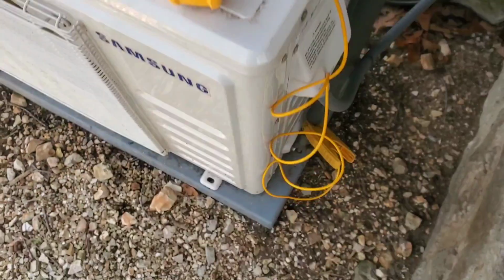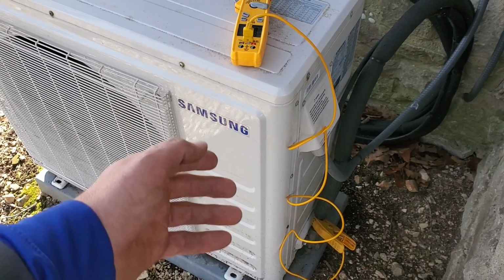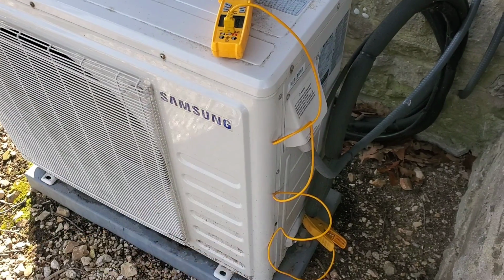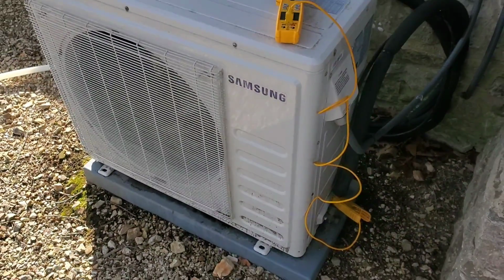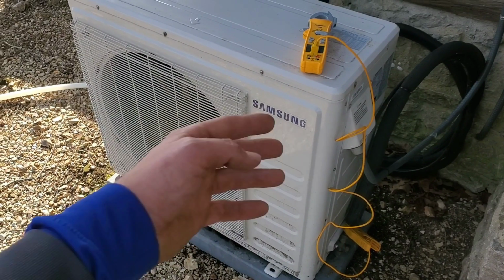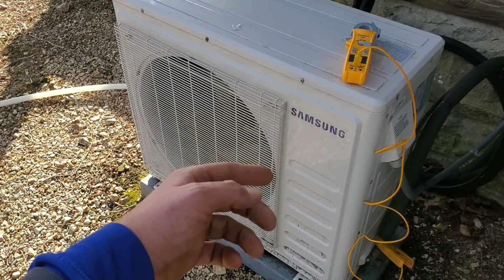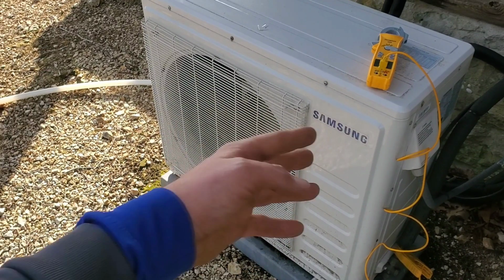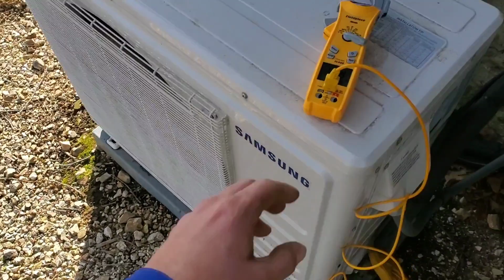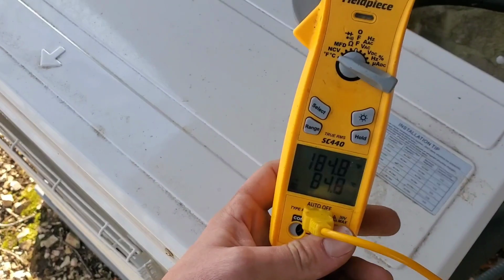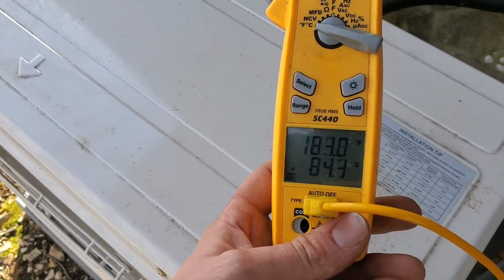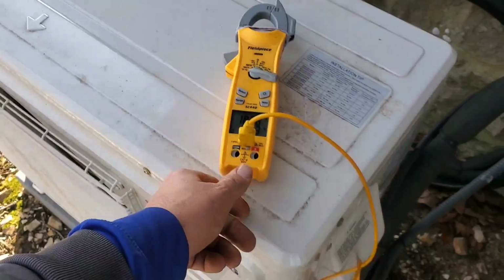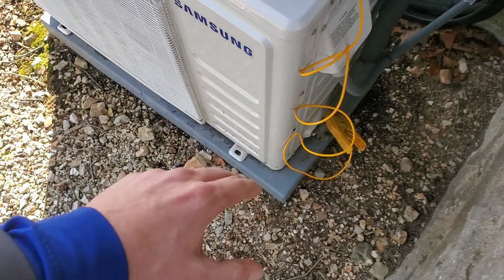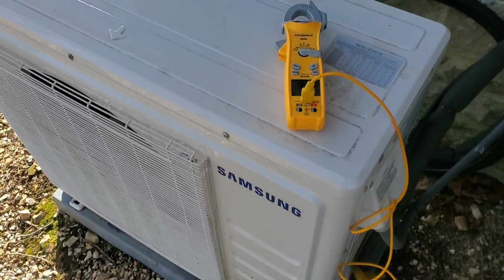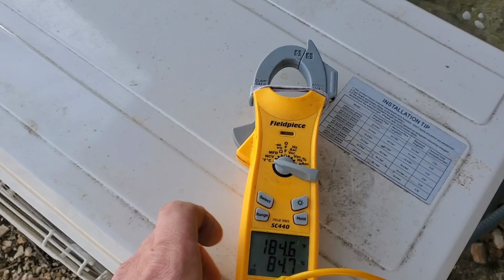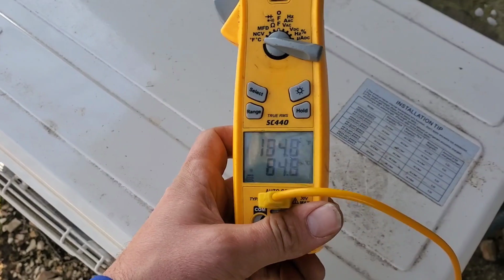It's getting close. It's definitely close to the 99 degrees because it's 180 degrees on the hot gas line, which is going into the indoor heat exchanger. So these units, they reach 99 degrees on the indoor coil, and when they measure that temperature, then they release the indoor fan. So after releasing the fan, it's definitely trying to reduce capacity. So it's steadying out at about 184 degrees. Definitely need to get my gauges, hook my gauges up, check and see what that pressure is.